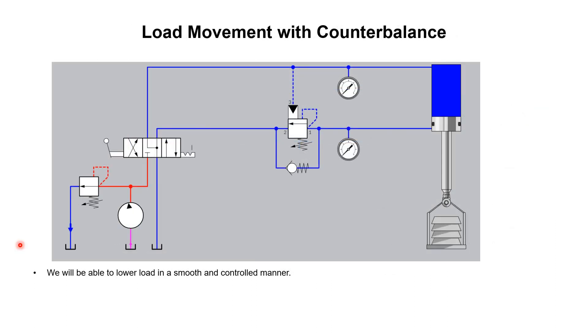To solve this problem we add a counterbalance valve. The basic definition is that a counterbalance valve is used to avoid the overrunning of the load during movement. This counterbalance valve is composed of two components: the first is the free flow check valve, and the second is the pilot operated pressure check valve. The free flow check valve provides unidirectional flow, while the pilot operated pressure check valve allows fluid passage only at a certain preset pressure value.